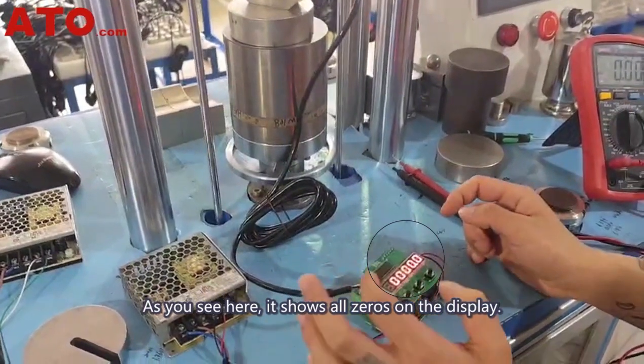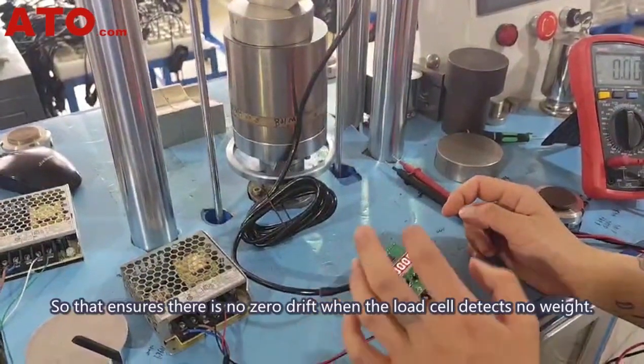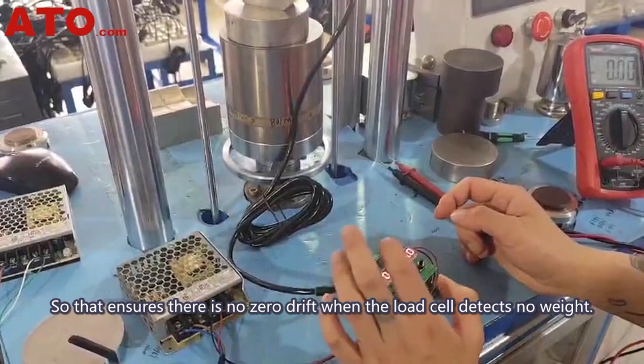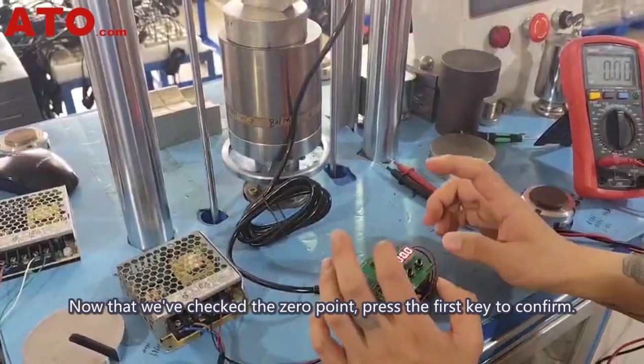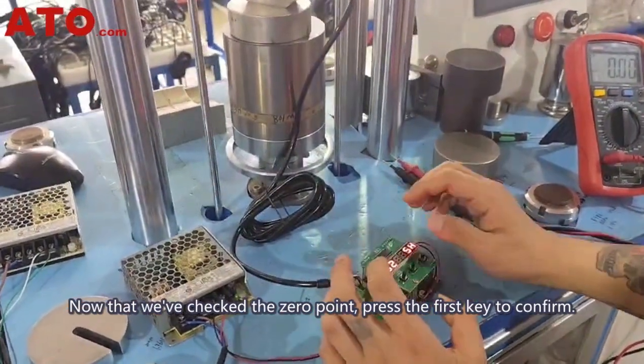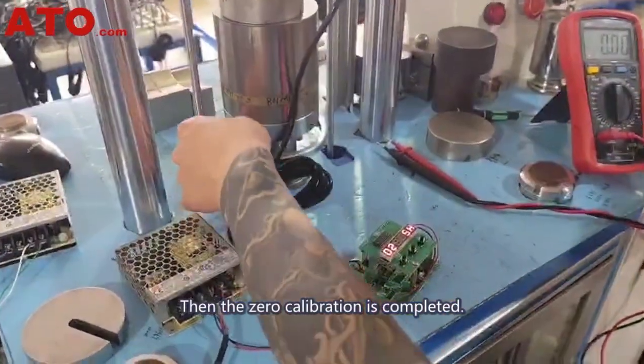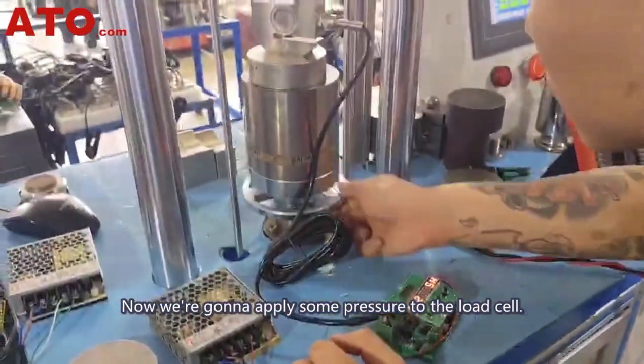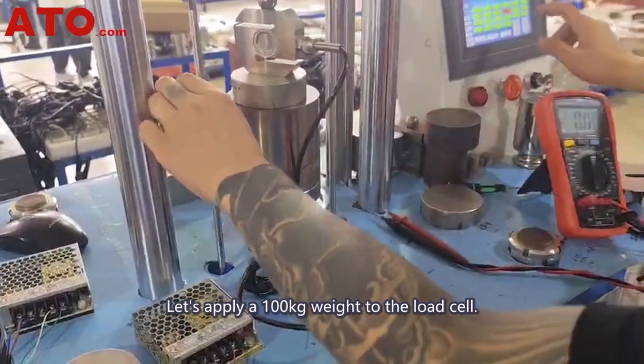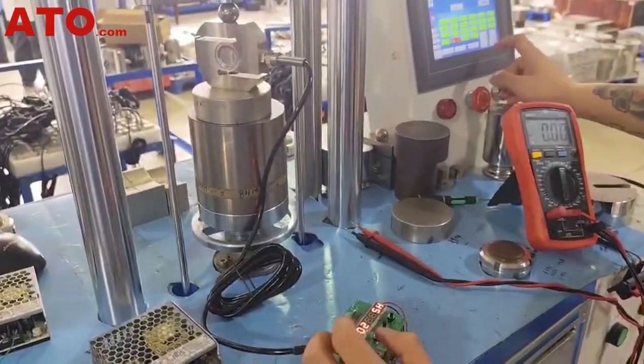As you see here, it shows all zeros on the display, so that ensures there is no zero drift when the load cell detects no weight. Now that we've checked the 0 point, press the first key to confirm. Then the zero calibration is completed. Now we're going to apply some pressure to the load cell. Let's apply a 100 kg weight to the load cell.